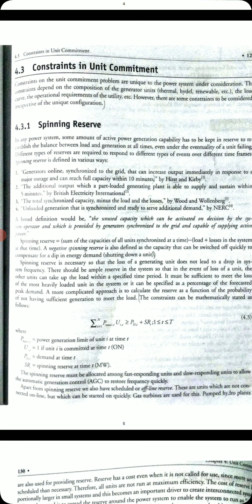Negative spinning reserve is also defined as the capacity that can be switched off quickly to compensate for a dip in energy demand. Mathematically we can give it as summation of i is 1 to n, Pmax i,t into U i,t, greater than or equal to PD,t plus SR,t, where t is between 1 to T.